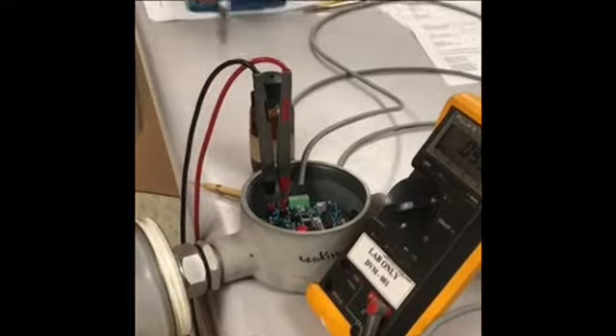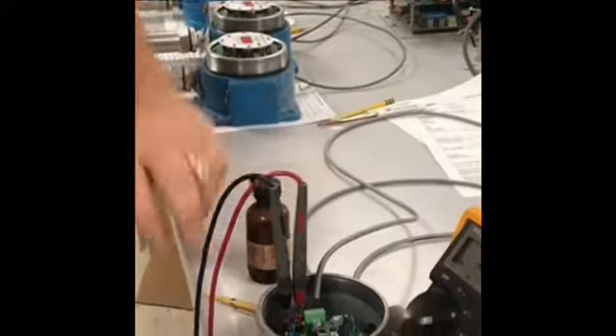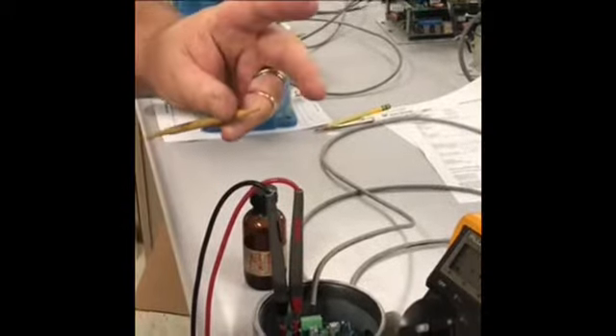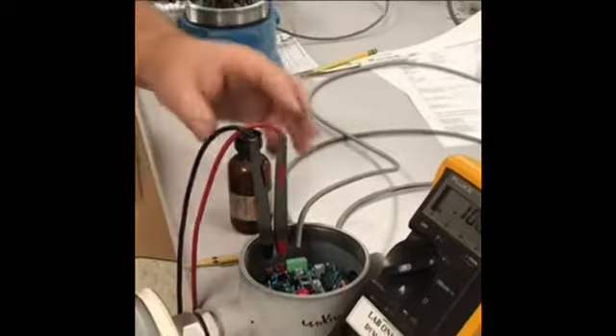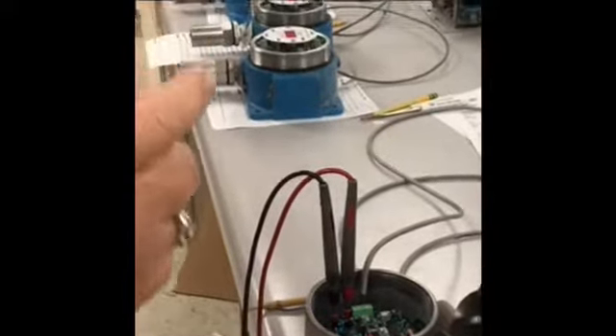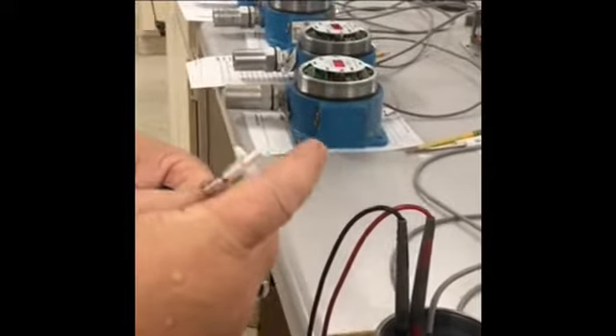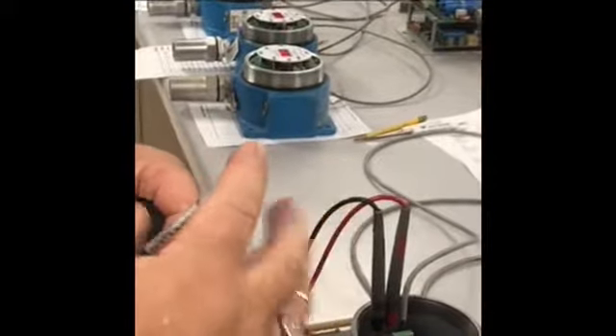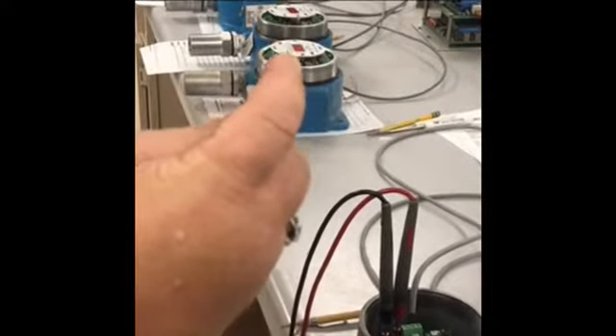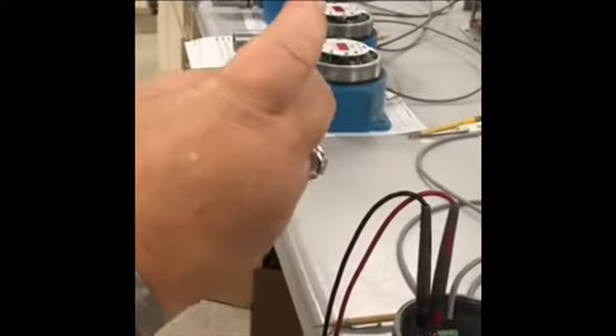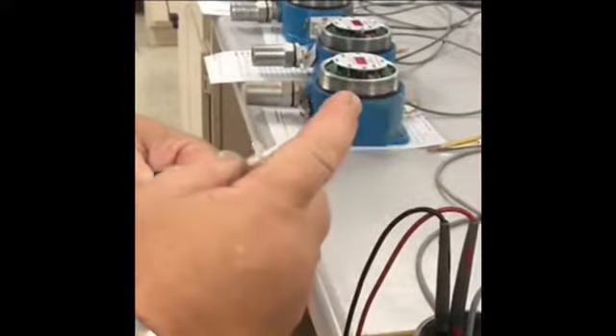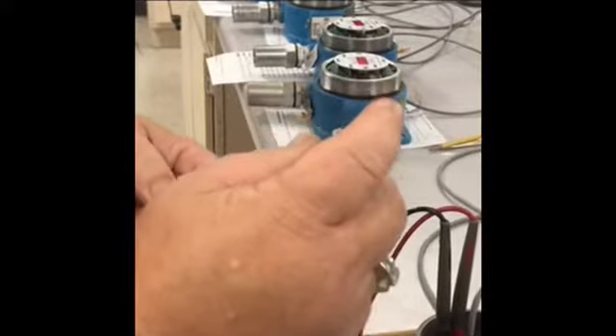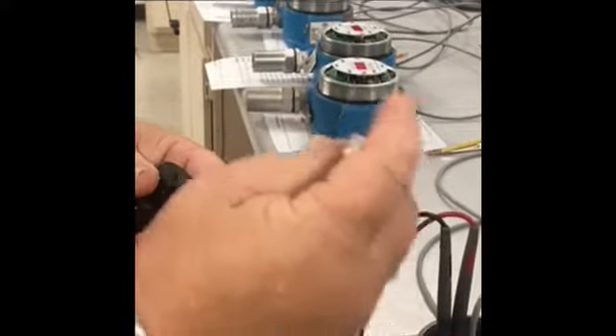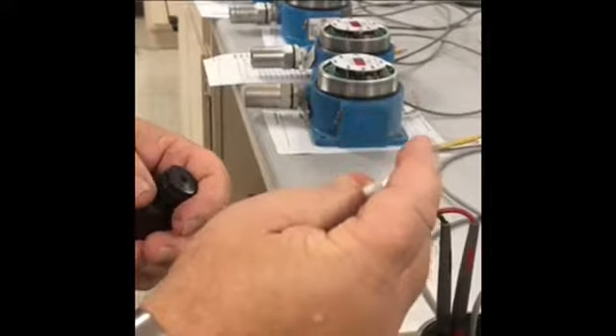You're going to need the syringe to get the gas out of the pure gas sample that we're going to use to calibrate. You're also going to need a screwdriver to turn the potentiometer to make your adjustment. So this time we're going to show you how to take the gas out of the bottle. You want to make sure to keep your finger over the plunger before you put the needle into the bottle, because if you don't, there's pressure inside this bottle. It's going to push this plunger up, and if your finger's not on it, it's going to push it all the way out. The gas is going to escape out of the bottle, and you're going to lose all your gas. So make sure your finger's over the plunger before you put it in.